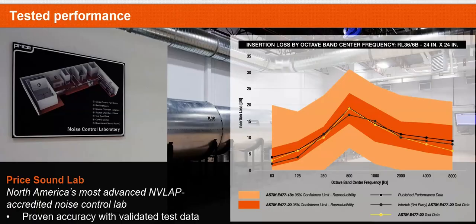What that means is if you look at the graph in front of you, the raw tested data on each frequency, for example, on the 63 hertz, we're taking 4 decibels off. On the 125, we're taking 5 decibels off. The most amount of performance on this specific tested unit, which is a 36-inch long 24 by 24 silencer, is at the 500 hertz. You have about 18 decibels off. Now, you test that in a lab with very accurate equipment.